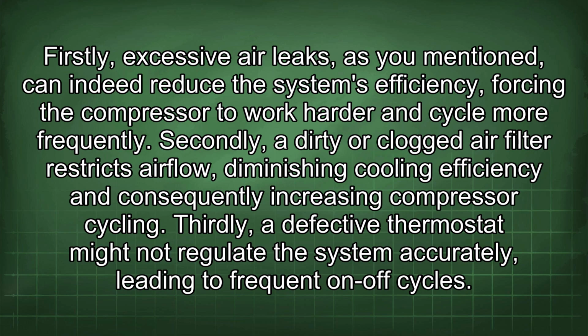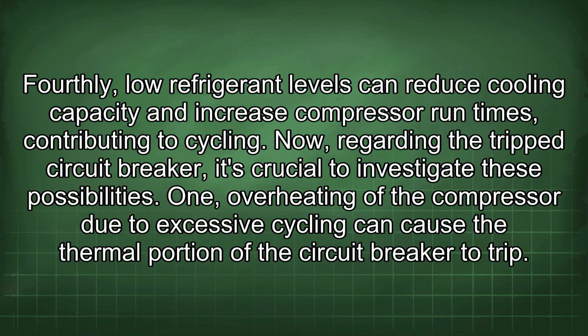cycle more frequently. Secondly, a dirty or clogged air filter restricts airflow, diminishing cooling efficiency and consequently increasing compressor cycling. Thirdly, a defective thermostat might not regulate the system accurately, leading to frequent on-off cycles. Fourthly, low refrigerant levels can reduce cooling capacity and increase compressor run times, contributing to cycling. Now, regarding the tripped circuit breaker, it's crucial to investigate these possibilities.